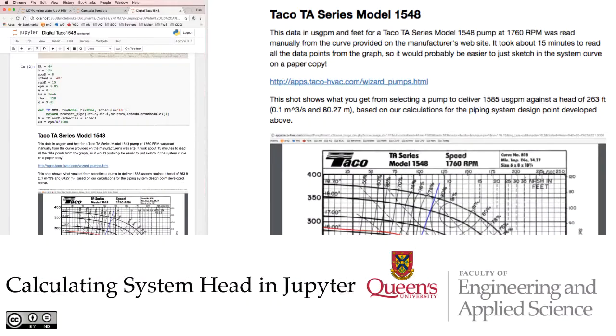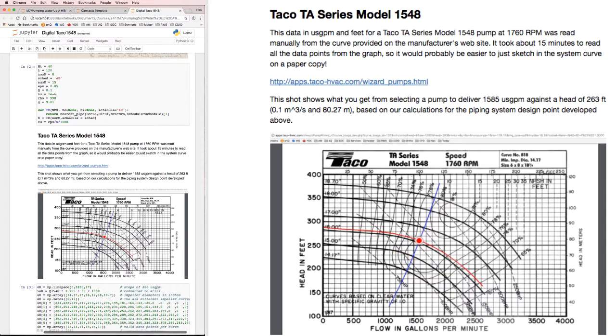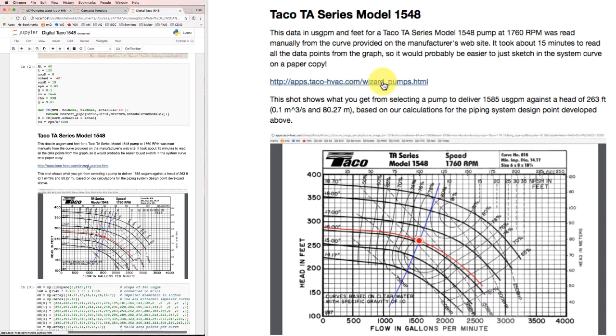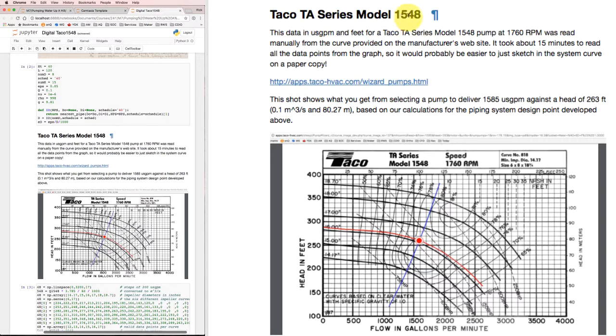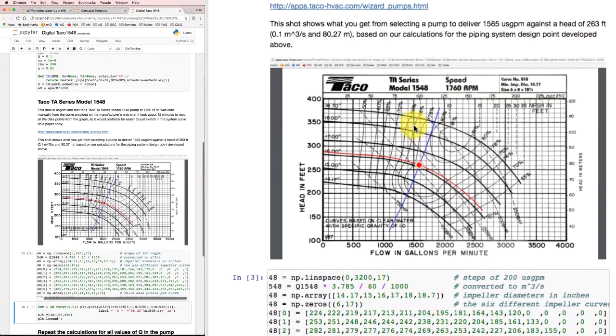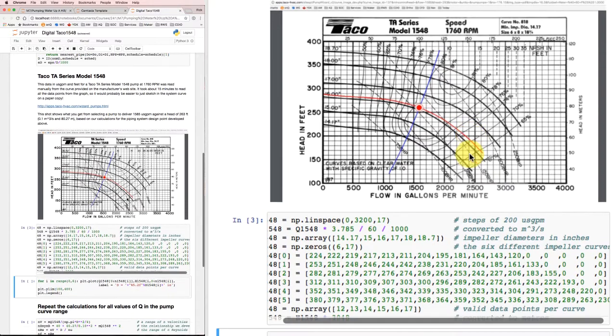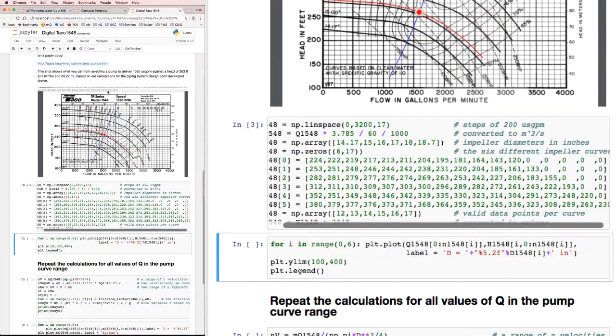Well, we calculated the performance for our system under one operating condition, and on that basis, we decided that from the TACO pump selector, this model 1548 pump made sense. So we got the performance curves for that 1548 and I went and digitized them.